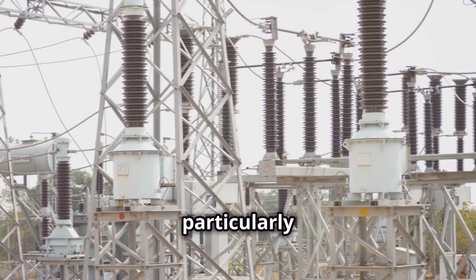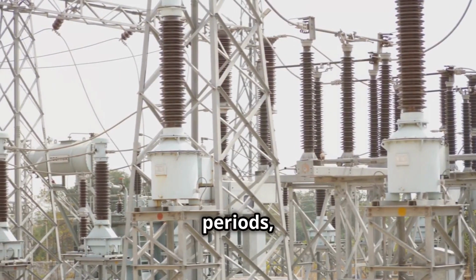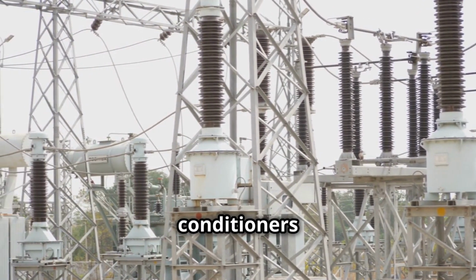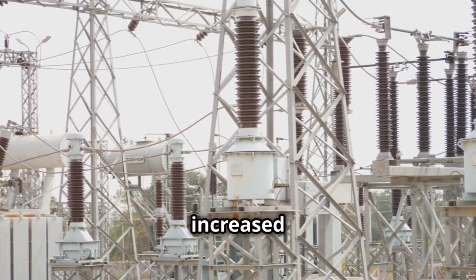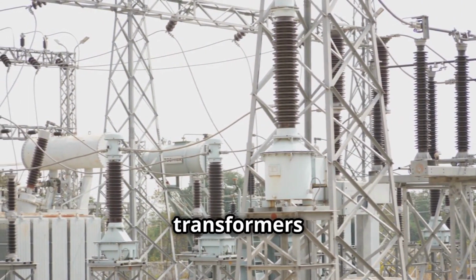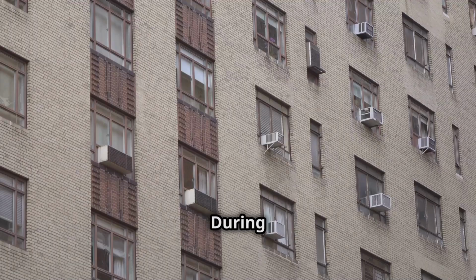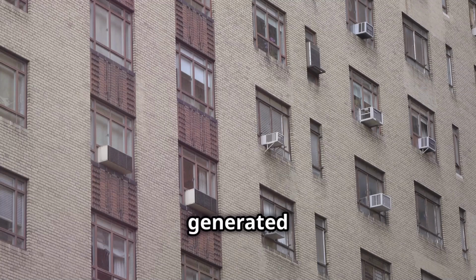This scenario is particularly common during peak demand periods, such as scorching hot days when air conditioners are running non-stop. The increased demand for electricity can push transformers beyond their capacity. During these times, the excessive heat generated by the high electrical load can cause the transformer's internal components to overheat. This overheating can lead to insulation breakdown, short circuits, and ultimately, transformer failure.